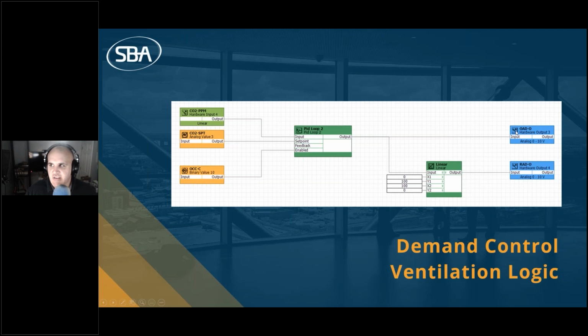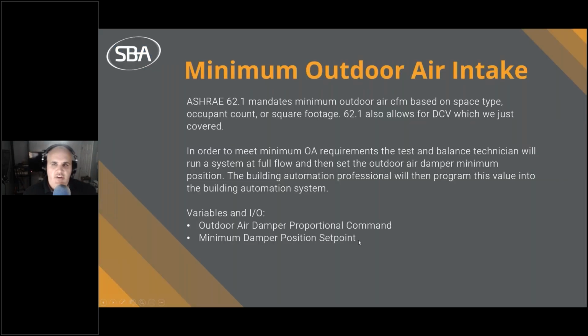And the whole purpose here is that you've got your outdoor air command, and then the return air damper will be reverse. With this kind of scaler, you don't have to worry about high or low limits because this PID output on this programming software, at least, is never going to drop below 0 or go above 100. All right, let's take a look at minimum outdoor air intake.